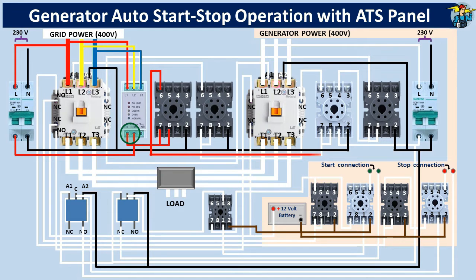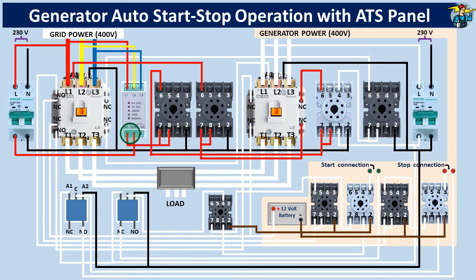The relay is energized after this delay period. Normally open points 8 and 6 will now be closed, allowing control power to timer number 2. This timer maintains a time lapse, preventing the load from getting power from the grid immediately after generator supply is removed. The 2 to 3 second blackout during the switch from generator to grid power is due to this safety time delay. The control supply to the operating coil A1 of the mains contactor now enables 3-phase supply to the load. This control power line to A1 passes through the normally closed auxiliary contact points of the generator contactor, allowing safety interlocking between the two magnetic contactors.